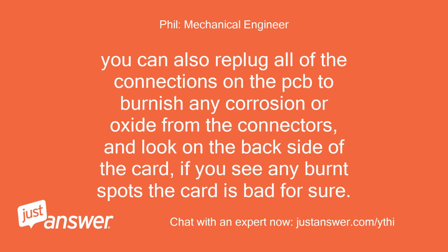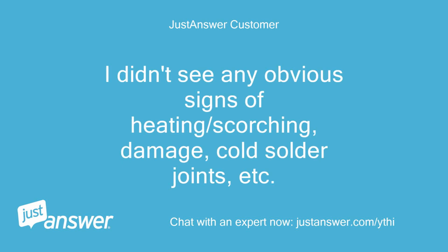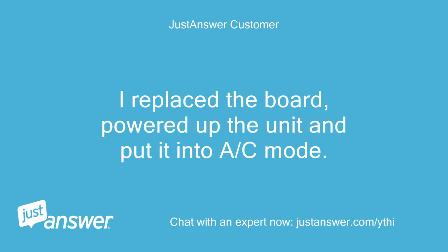You can also replug all of the connections on the PCB to burnish any corrosion or oxide from the connectors, and look on the back side of the card. If you see any burnt spots, the card is bad for sure. I replugged all of the connections to the board this morning and removed it for inspection. I didn't see any obvious signs of heating/scorching, damage, cold solder joints, etc. I replaced the board, powered up the unit and put it into AC mode.